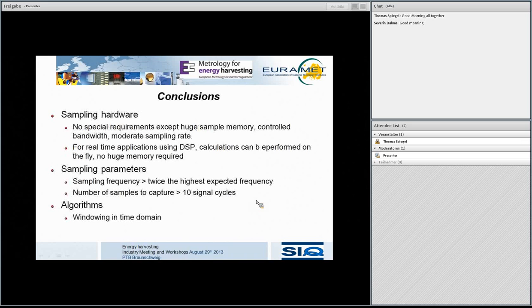For the conclusions, for the sampling hardware necessary to measure voltage, power, current and energy, there are actually no real special requirements except huge memory, which we use to store all these samples. However, if you know what window you will take, or what your lowest frequency in the signal is, and you decide that your window is fixed, and you are using a DSP or such a thing, the calculations can be performed on the fly, and you actually don't need any memory. That's a real advantage of this system and of this windowing approach. You don't need any post-analysis of the data, because you can just collect them, sum them, and multiply them on the fly with the windowing function, and at the end you get the power out or the RMS out. So that's a good thing.